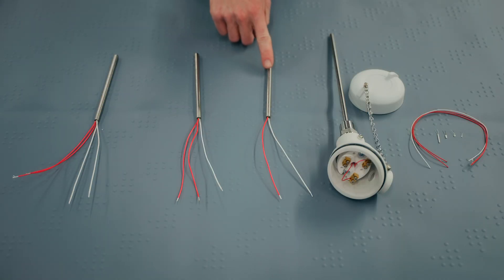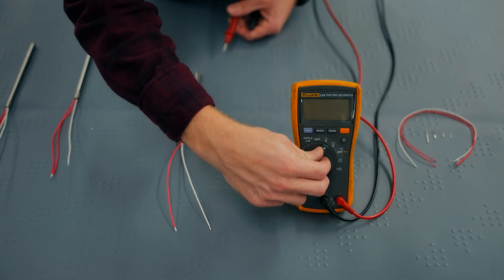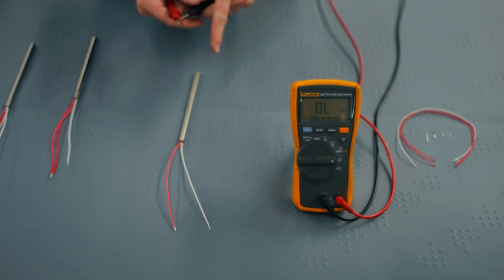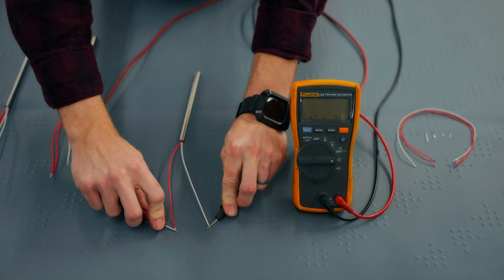RTDs can be constructed in two, three, or four wires. On a two-wire RTD, simply set the multimeter to measure the resistance and check the resistance between the two leads. This RTD reads about 109 ohms, so it's functional.